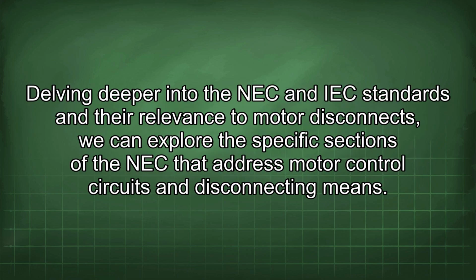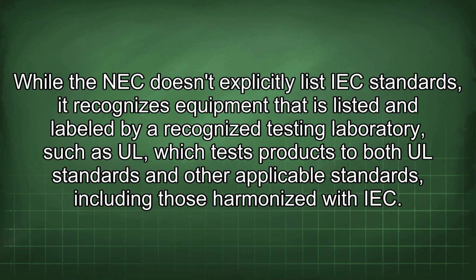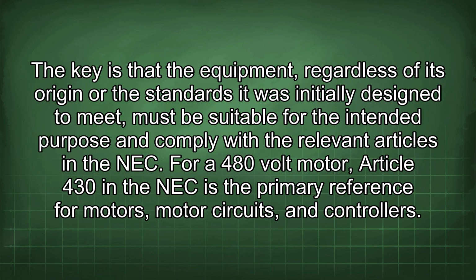Delving deeper into the NEC and IEC standards and their relevance to motor disconnects, we can explore the specific sections of the NEC that address motor control circuits and disconnecting means. While the NEC doesn't explicitly list IEC standards, it recognizes equipment that is listed and labeled by a recognized testing laboratory, such as UL, which tests products to both UL standards and other applicable standards, including those harmonized with IEC. The key is that the equipment, regardless of its origin or the standards it was initially designed to meet, must be suitable for the intended purpose and comply with the relevant articles in the NEC.